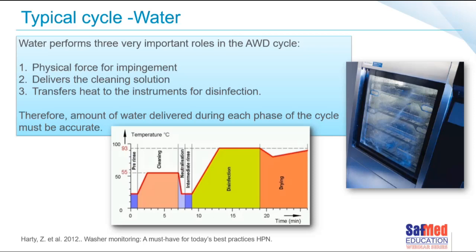If there is too much water, the chemical dilution could be inaccurate — the chemistry could be too diluted, meaning instruments may not clean properly. On the other hand, too little water means the chemistry will be very concentrated, which can leave unseen residuals on instruments and result in poor cleaning. Not enough water also means insufficient force to clean. In some instances the machine will alarm and may even abort the cycle depending on the incoming water pressure. Water pressure is therefore very important when installing washer disinfectors.